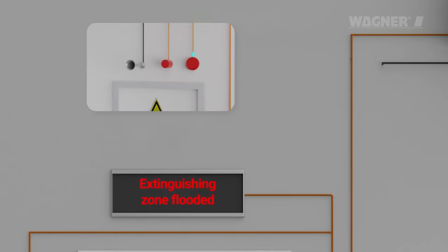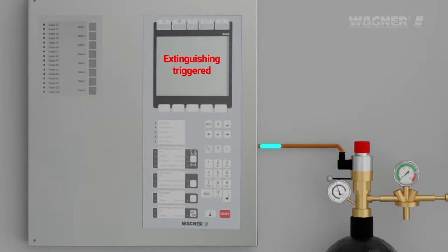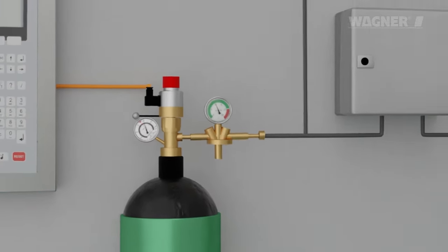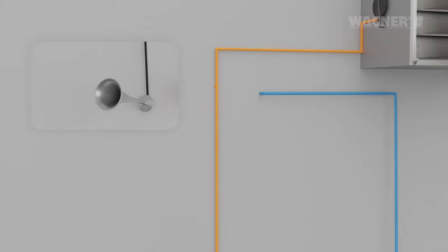The imminent start of fire extinguishing measures is indicated on the display panel and by a flashing light. The extinguishing control panel now initiates the extinguishing process. Pilot gas from the pilot gas container is forwarded to the pneumatic alarm and triggers it.